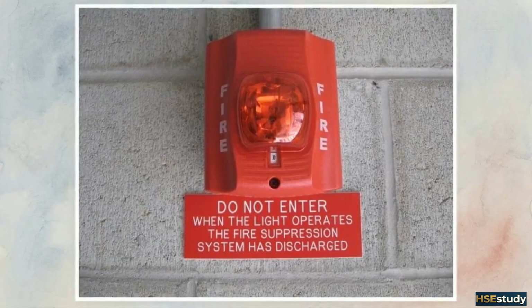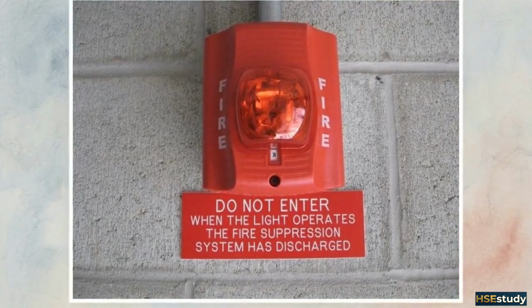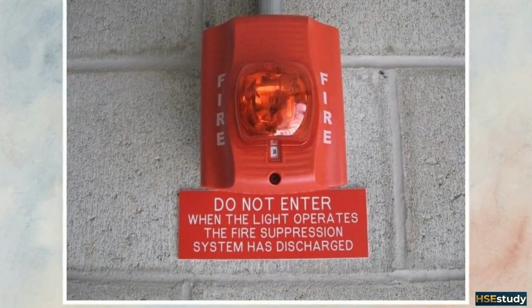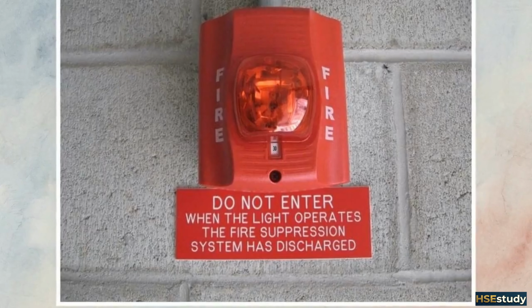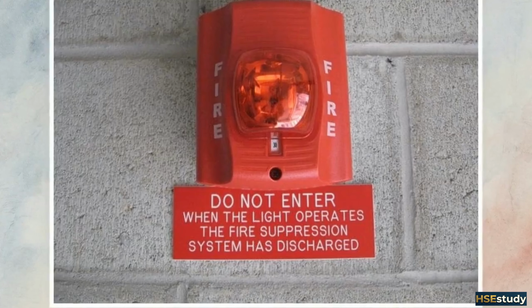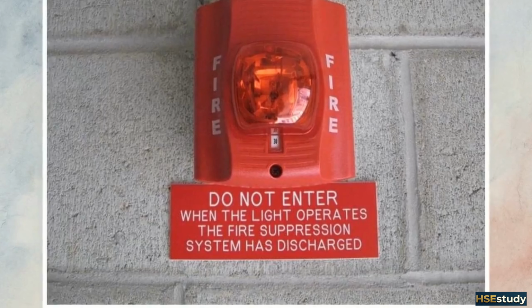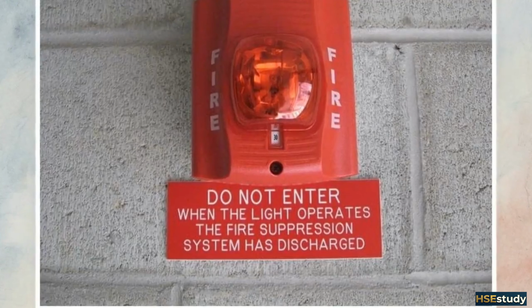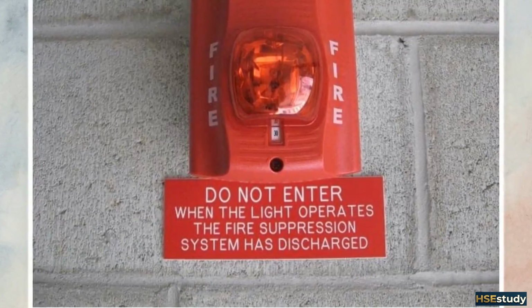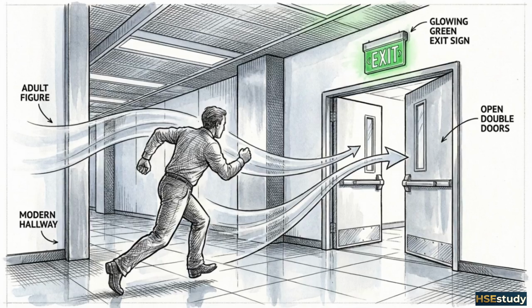Safety codes mandate visual warnings, including placards and synchronized strobes, to alert personnel to the hazard of the agent itself. Following a discharge, door discipline is non-negotiable. Only enter with SCBA gear or clearance from the authority having jurisdiction. The system's sequential logic provides a calculated window for human evacuation.